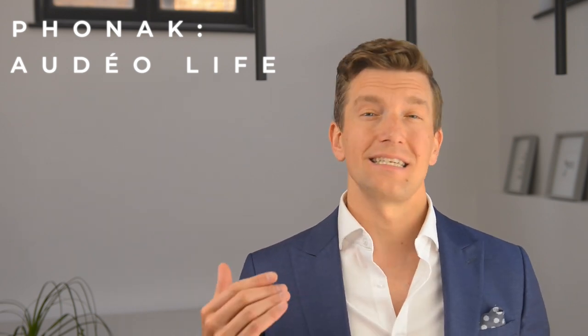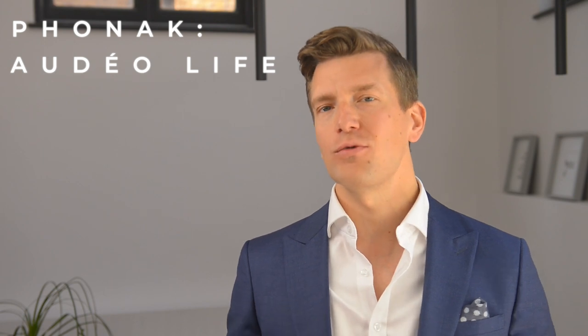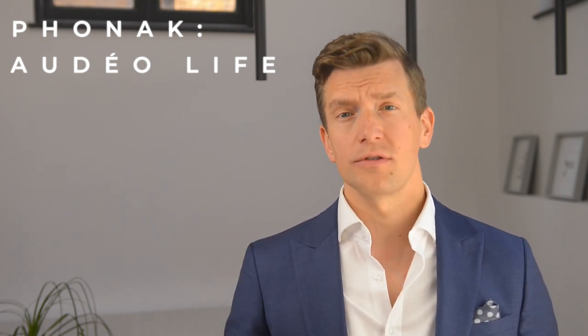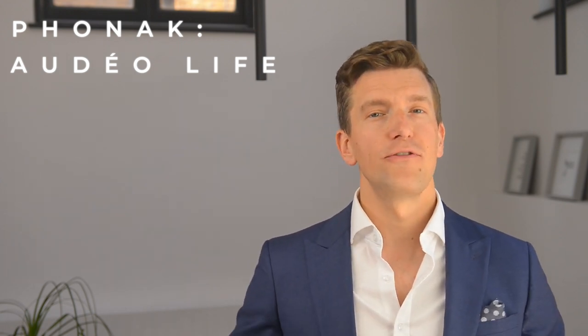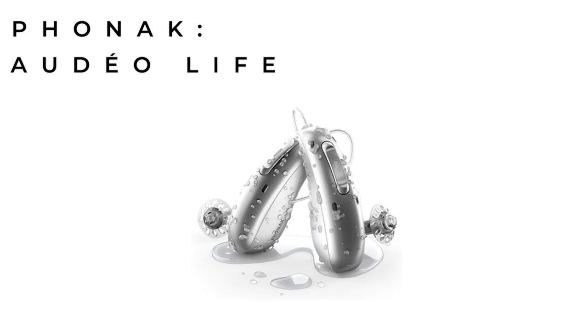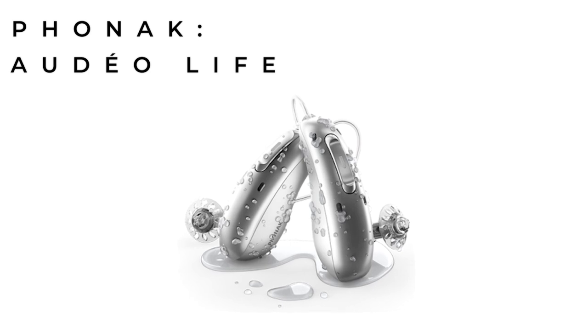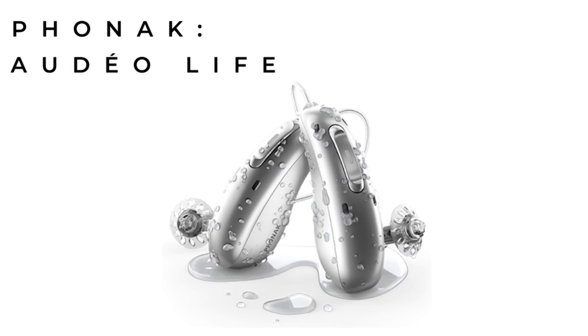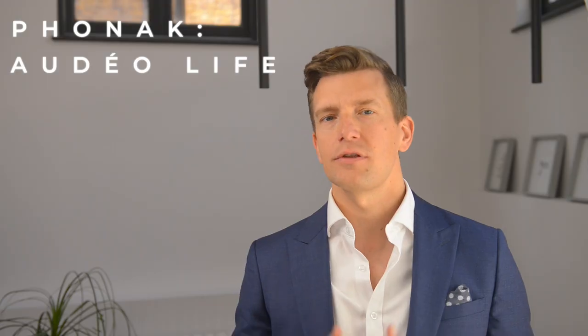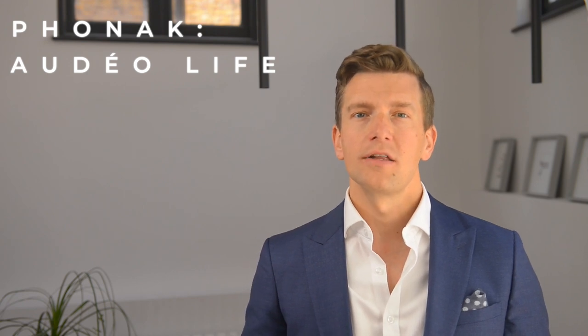So what's so unique about the Phonak Life hearing aids? Whilst the majority of hearing aids released by all manufacturers now have an IP68 rating — which means they can technically be submerged in a meter and a half of water for 30 minutes and still function — Phonak are boasting that this new receiver-in-canal style hearing aid is the world's first fully waterproof rechargeable hearing aid. To achieve this, they've added additional microphone protection, sealed the seams with silicone, coated the components with a parylene coating, and redesigned the charging system.